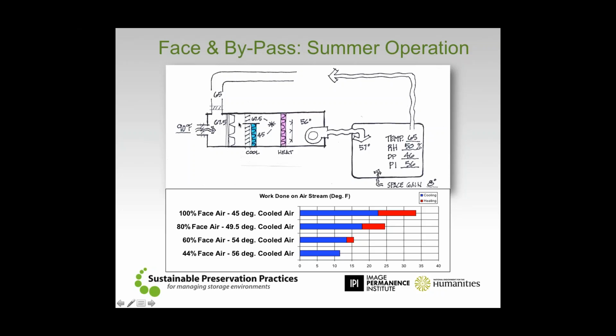What we work with in this particular scenario is saying, if there's moisture coming through, the theory behind this is that some of it's going to get caught here at the cooling coil in the first pass and get dehumidified. Some's going to go by, but it's going to blend, come back through the system, and on the next pass, some of that air that we missed the first time around, we're going to catch the second time around, and we're going to dehumidify it on that pass. So the key is that you have to be able to do more dehumidification than the amount of moisture that you're pulling into the system.